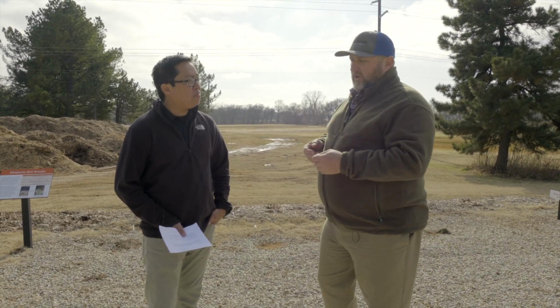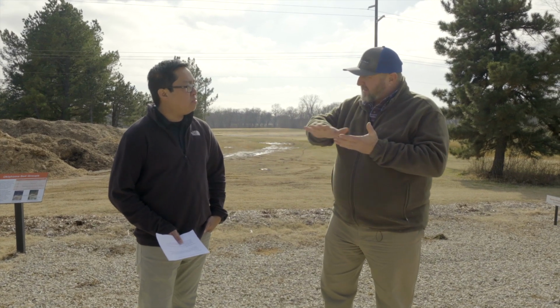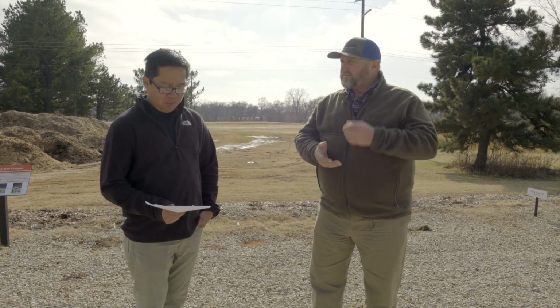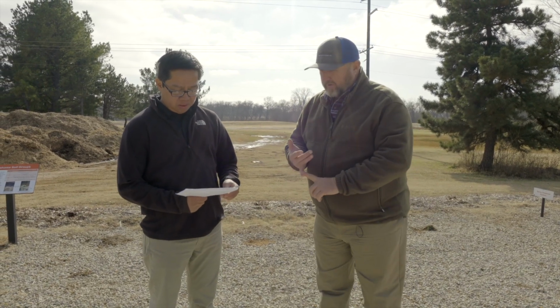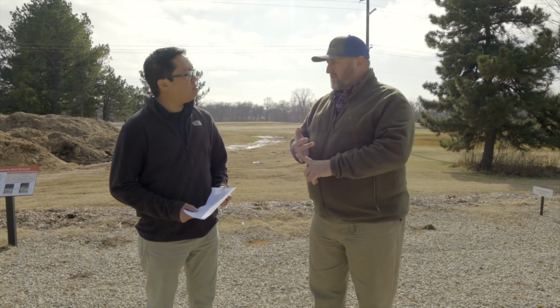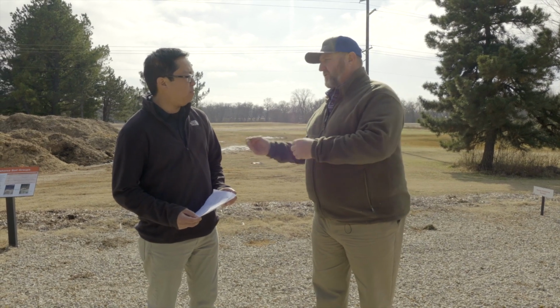Okay. You can always look into your clarifier and see if you have a nice rich chocolate layer on top of that. It's probably alive. If your clarifier is gray, it's dead. Very good. That's a sign that there's something wrong. Either the air compressor's not working or you're putting something in to kill it. And it's very easy to tell. A technician can come out and check the airflow and the pressure, and they can tell you your plant's mechanically sound.